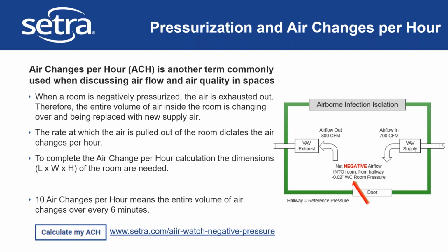Later in this presentation, I will show you how you can use portable units to incorporate additional air changes per hour in your space. But we'll stick with this example now to help you understand how this is used, how it's calculated, and how it's helping to increase the safety and protection of people throughout these communities. So you can see in the diagram, the airflow out is greater than the airflow in. That helps to create the negative pressure, and it helps to generate the air changes per hour. That flow rate being shown here at 800 CFM in this hospital-oriented example is the flow rate of air that is exhausting the air out of the room, and that dictates the air changes per hour. The other half of the calculation that's needed for air changes per hour is the dimensions of the room.